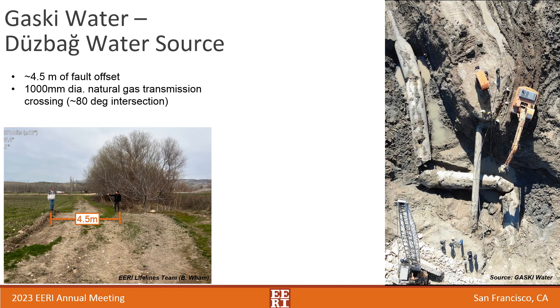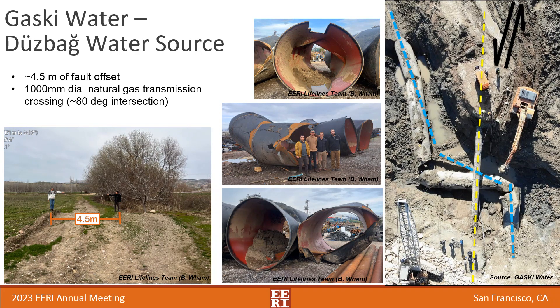At another location on the same pipeline, there was a 4.5-meter fault rupture crossing. A gas transmission line runs over the top of the water pipe, so the water pipe had to cross it at an angle of between 75 and 90 degrees, creating a jog in the pipe — almost exactly where the fault ruptured. The fault rupture ran generally in line with the gas transmission pipeline, so there wasn't much damage determined there. However, there was significant damage to the water line, and those damaged sections have now been removed and replaced.